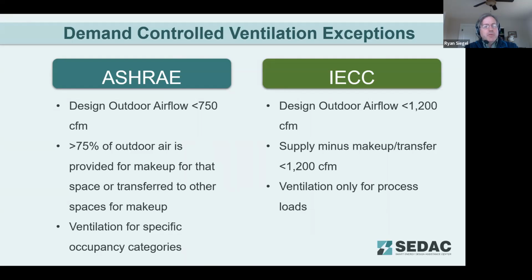And then with ASHRAE, there is a provision where if you have more than 75% of outdoor air being done through transfer air or being provided through to other spaces for makeup air, then you can avoid needing DCV. Probably a common location that we'd see this would be places with large exhaust rates, laboratories, restaurants would be a big one, where you've got that kitchen ventilation rate that you have to be providing a lot of makeup air. So here, where commonly we'll see restaurants, they're going to go ahead and use the dining room for that makeup air and transfer it through into the kitchen. So that's one area that we would commonly see that DCV exception used.